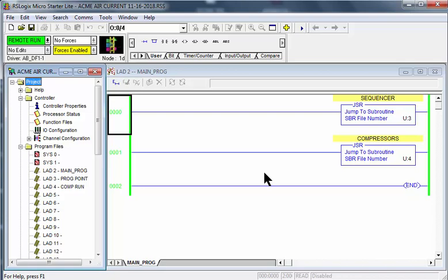There are 3 reasons for beginning with the output. Number 1, an output can only be used once in a program. Number 2, outputs have a higher current than inputs and therefore have a greater risk of failing. And number 3, it is far easier to navigate through a program to find out what condition is lacking to make an output true.